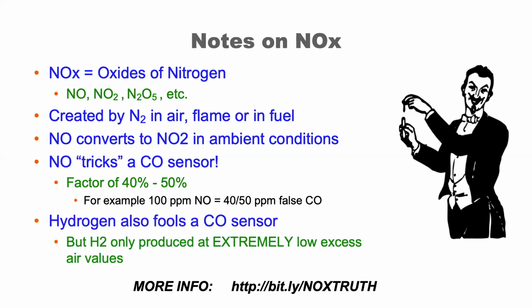There's also a fact that hydrogen fools the CO sensor. It can make it think that there's CO present when there's hydrogen present, but you only get that hydrogen if you think back to the hydrocarbon fuel. Only when you have very, very low amounts of excess air will you find hydrogen being produced, typically, in a combustion system. So this isn't something usually encountered in residential or commercial, who's usually our audience.